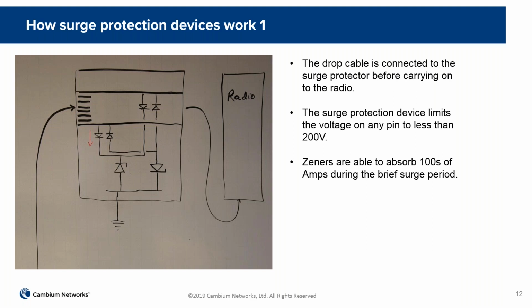So here we have an example typically of the components that you have within a surge protector, attached to each of the Ethernet wires. We've got 8 Ethernet wires here, and each of those wires has a pair of diodes in a bridge form attached to it, such that positive pulses will go through the diodes on the left down to the large Zener at the bottom there, and negative pulses will transfer through the diodes on the right, and through the other Zener. So those devices are able to handle very high currents for short periods of time, which, as we saw from the previous slide, we're looking at a pulse period of about a millisecond or so.